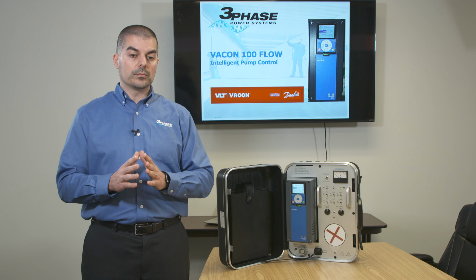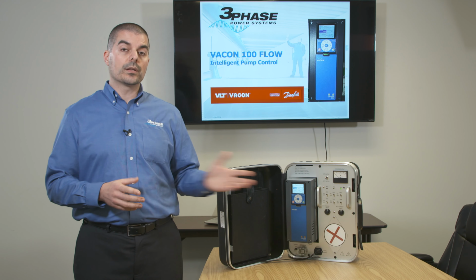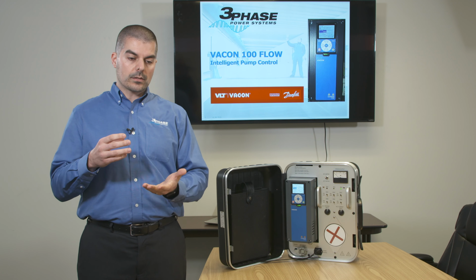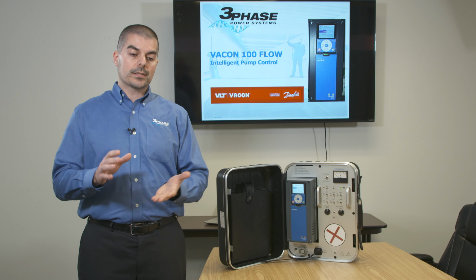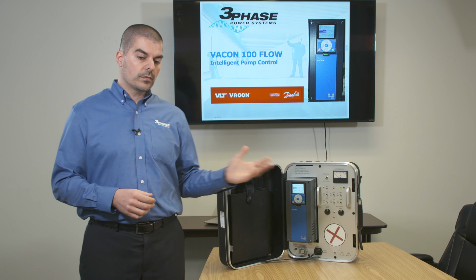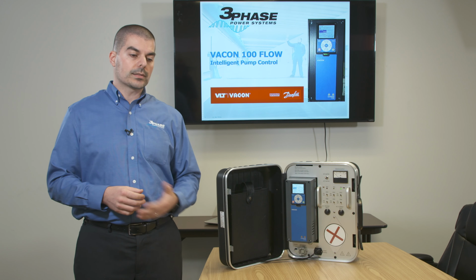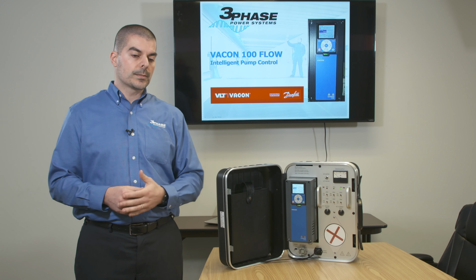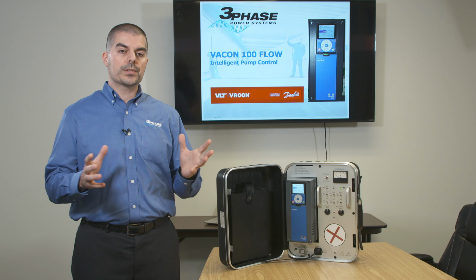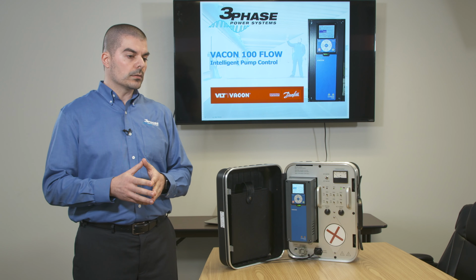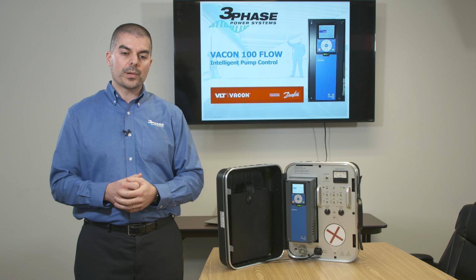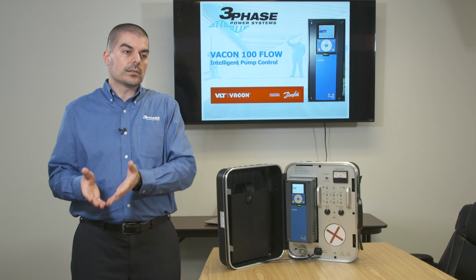One of the best features about this drive is the fact that it has replaced the electrolytic capacitors with thin film capacitors that can be found in the 100 Flow. Thin film capacitors on the DC bus do not dry out like electrolytic capacitors. There is a fantastic thing about these thin film capacitors: if you leave a drive on a shelf traditionally and it's not being used, electrolytic capacitors would dry out, and then a drive cannot be used. This is as simple as it gets.